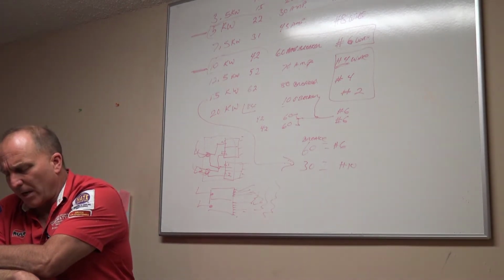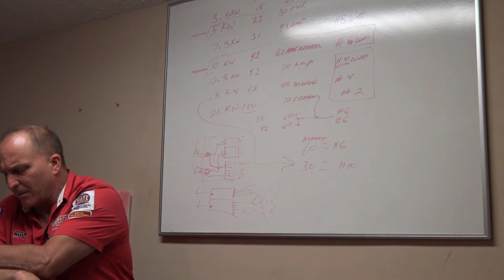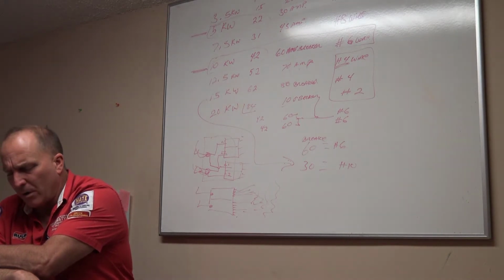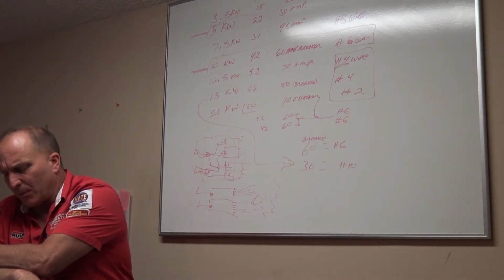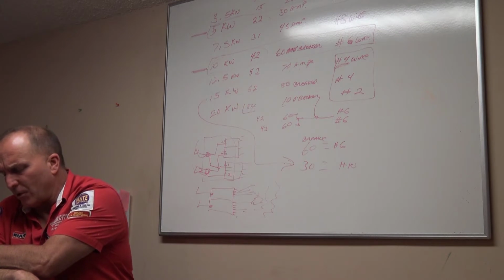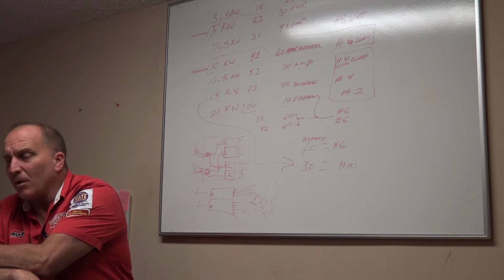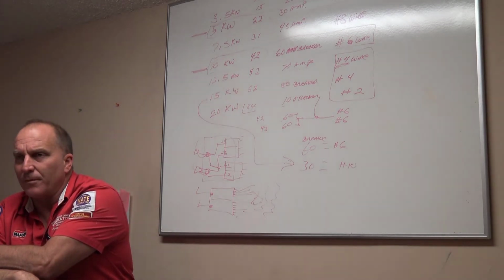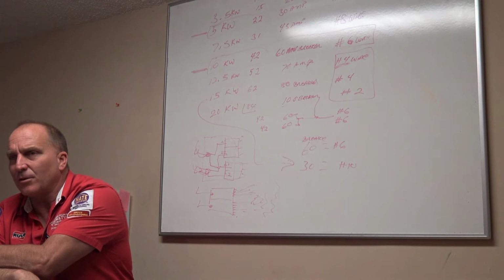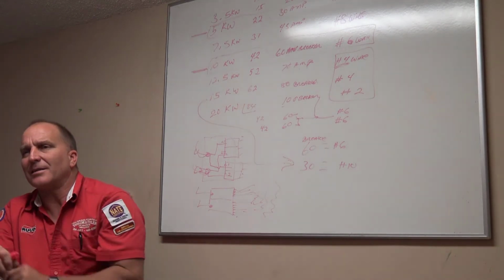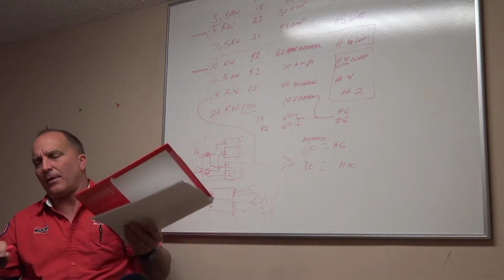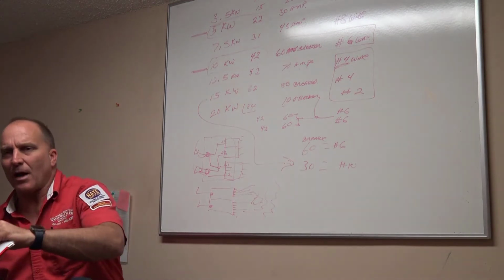Low voltage, check the connections and make sure the system is set up properly for how it is designed. Example, 2-stage heat, W1, W2. Are they jumped? Do you have a 2-stage thermostat? So if W1 and W2 is jumped off and you have a 2-stage thermostat, are you utilizing the efficiency of that air handler? The answer is no, you're not.